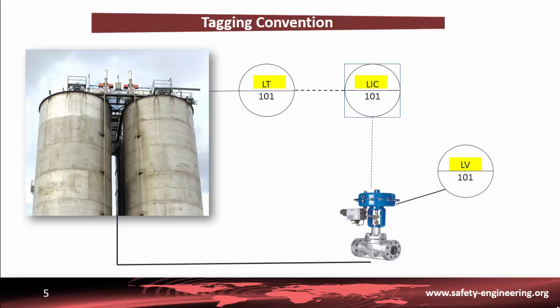The letters that make up the first few characters of a typical tag number — the leading letters — are used to identify the function performed by the field device or by the control system. Following this leading letter is a number, known as the loop number, which is used to uniquely identify one or more field devices used to perform a specific function. This combination of function letter and loop number enables a field device in a process area to be accurately identified.